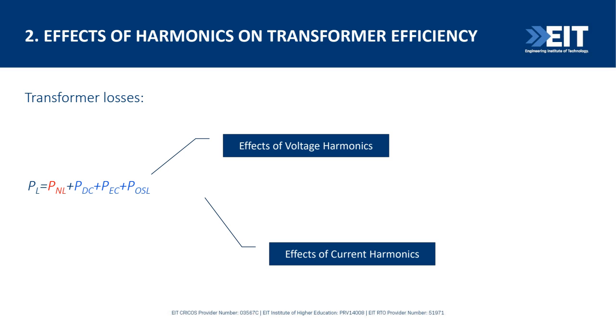When we're looking at transformer losses, we can imagine two types of losses: one is the effect of voltage harmonics, and the other is due to current harmonics. As I said, when we have harmonic components, we are drawing more current from a transformer to supply the same demand.